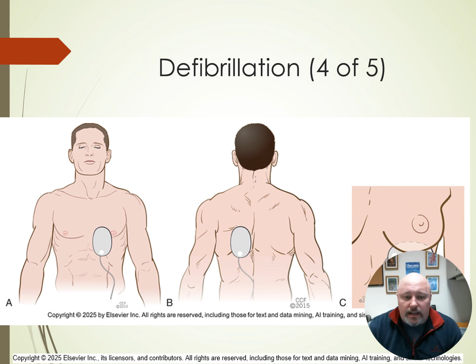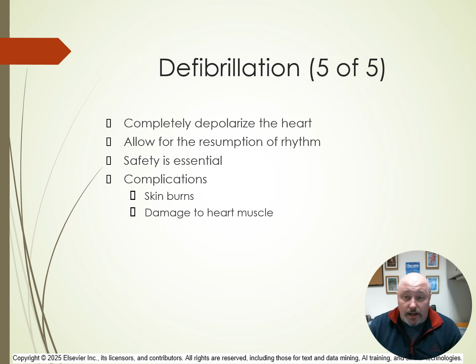Here we just have a diagram showing the correct placement of both the paddles as well as the pads. And here we have another diagram showing an alternate method for pad placement. You must implement safety checks to prevent shocking any surrounding personnel. I mean, safety is going to be a top priority in this. And always ensure that the area is clear before initiating a shock, whether it's via paddles or defibrillator pads.